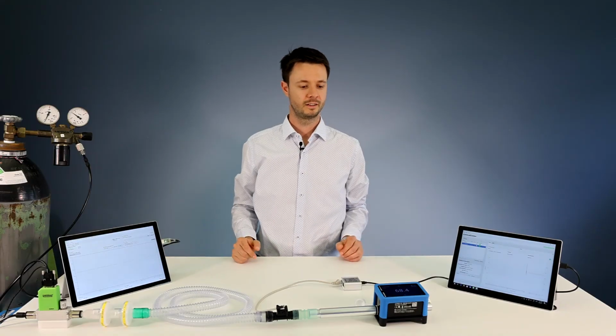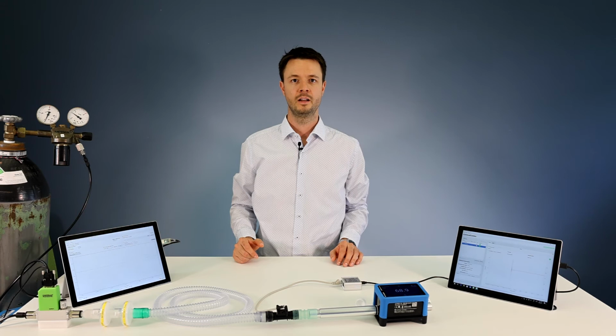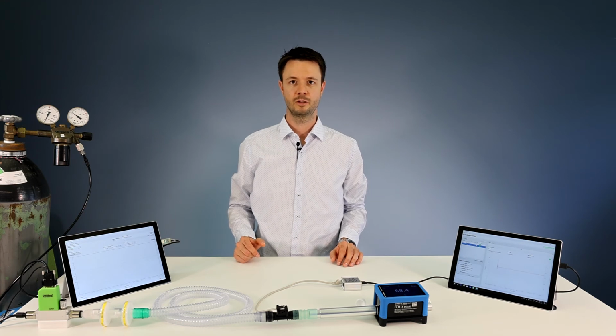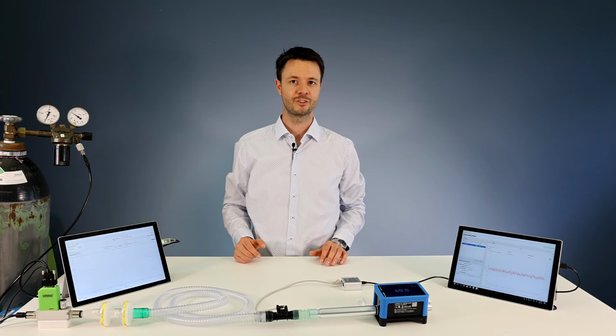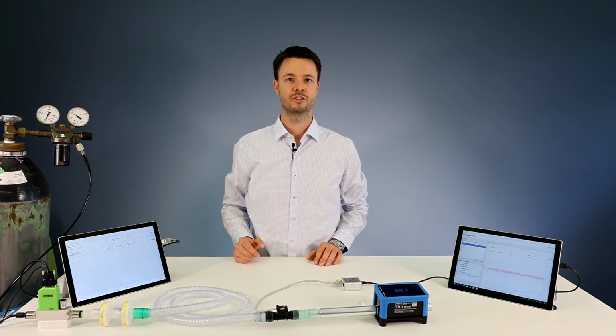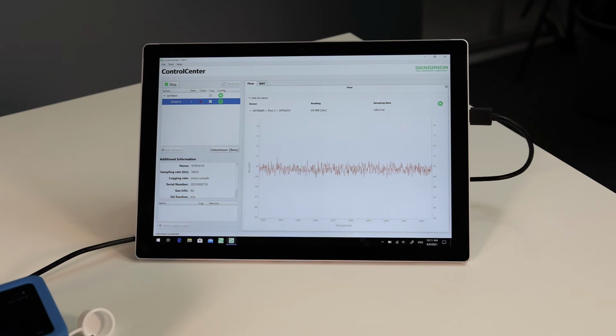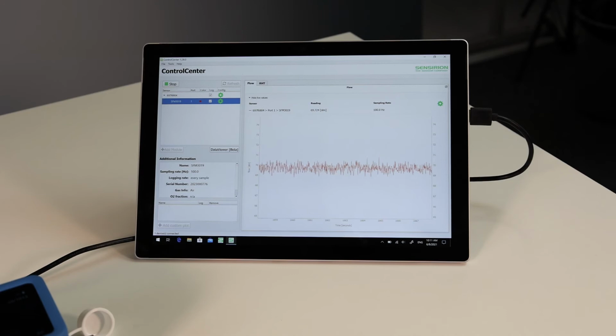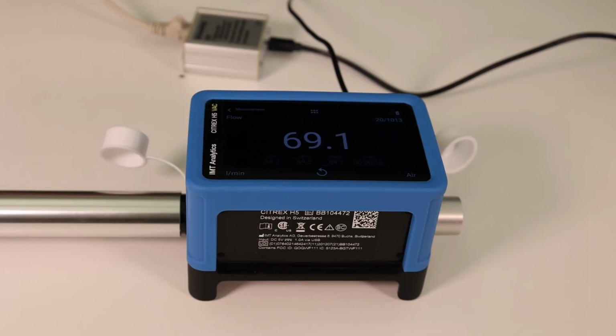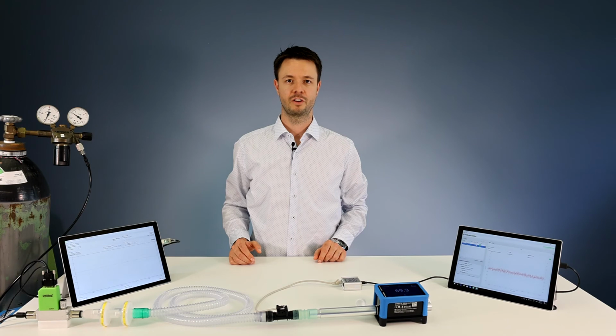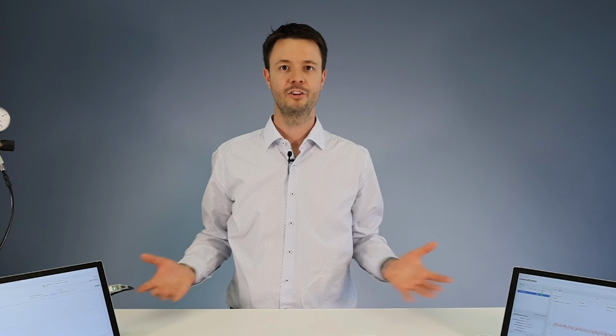What can you hear? Yes, there is less noise now. This is a good sign that the jets and turbulences have been removed, and I'm very curious to see what you get with these laminar flow conditions. Indeed, I get 69.7 liters per minute from the flow sensor and 69.1 liters per minute from the reference. Both values are very close to 70 liters per minute and well within the tolerance range of 67.2 and 72.8 liters per minute. That's great, we have an accurate reading at 70 liters per minute.